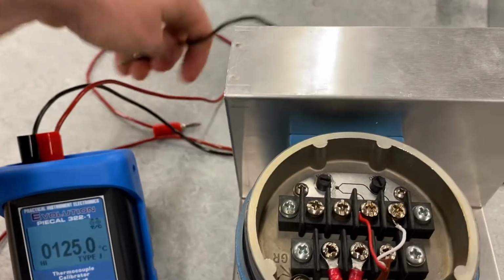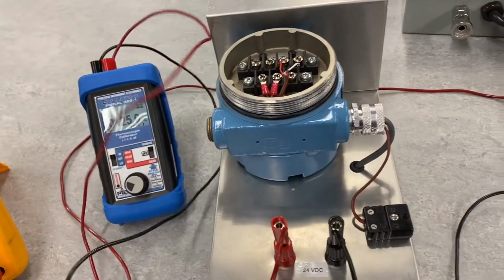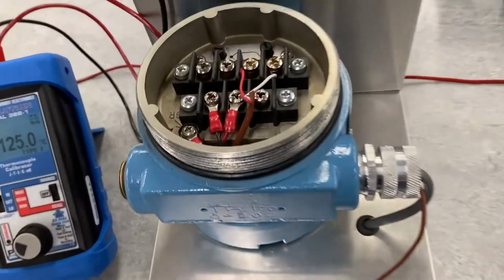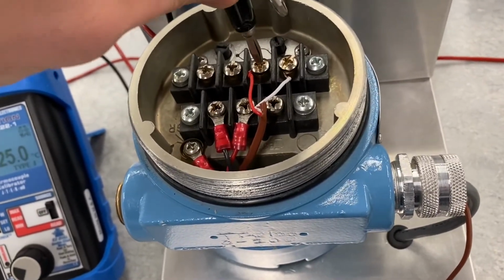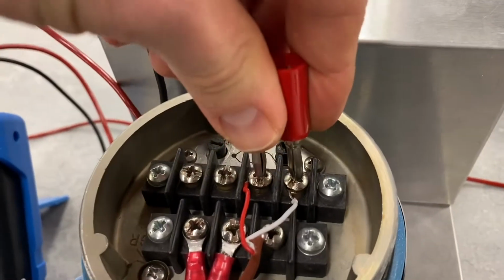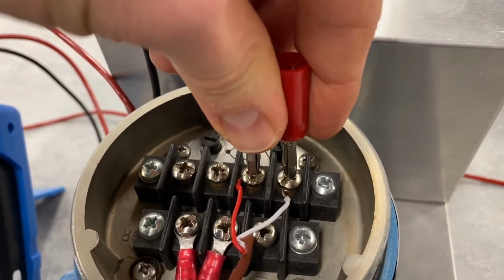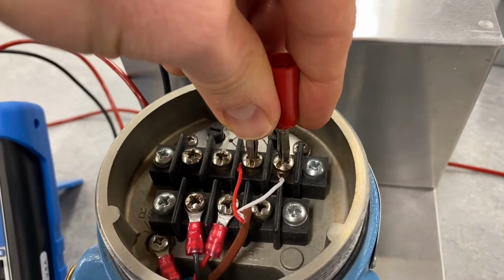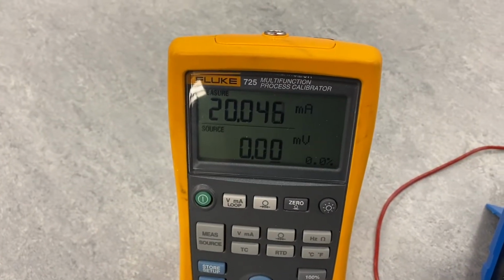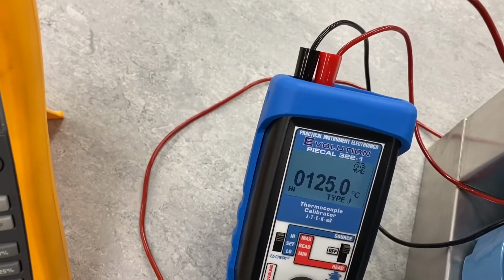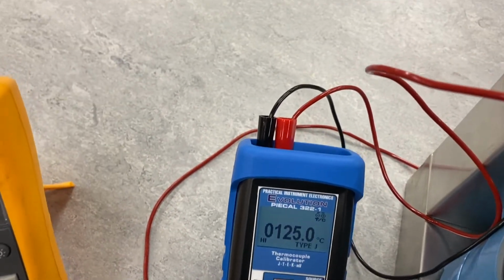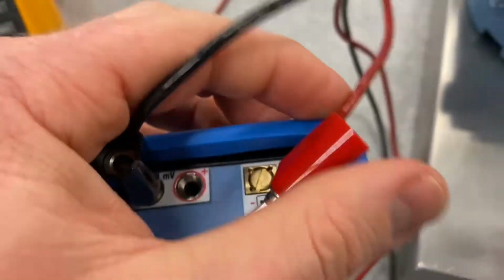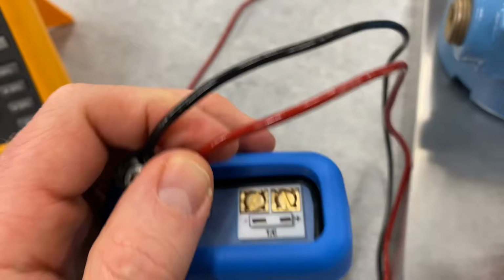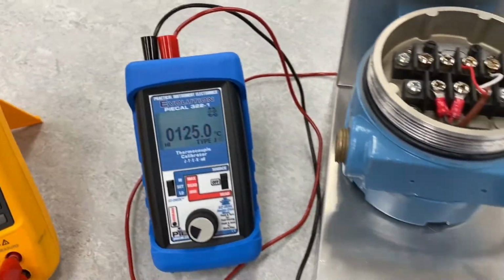Now we're going to just be taking our leads here and placing them across, red to the positive, black to the negative right there, across where our thermocouple would go to source our millivolt value in. And you can see over here our transmitter is reading pretty close to 20 milliamps at 125. So I've already calibrated this transmitter. And then just to confirm here, you can see if I pull these leads out, that the red is indeed hooked to the positive. Because of the color coding confusion of the thermocouple having a red negative lead, I wanted to clarify that.